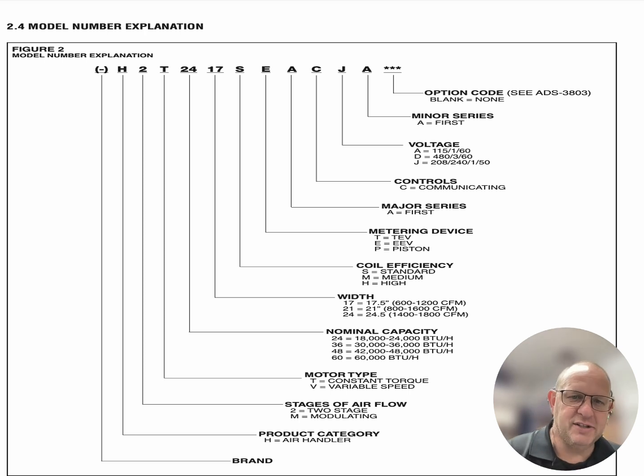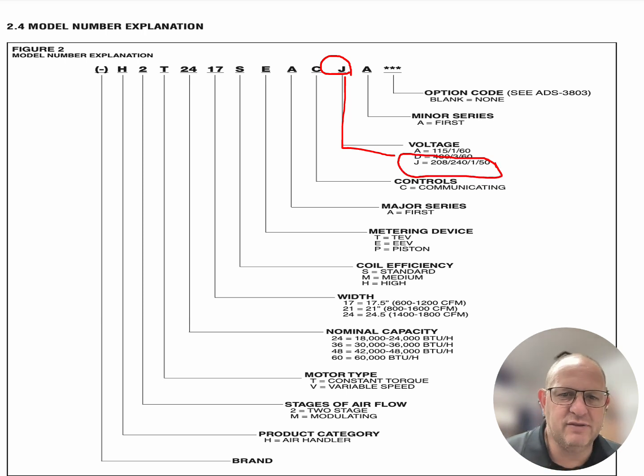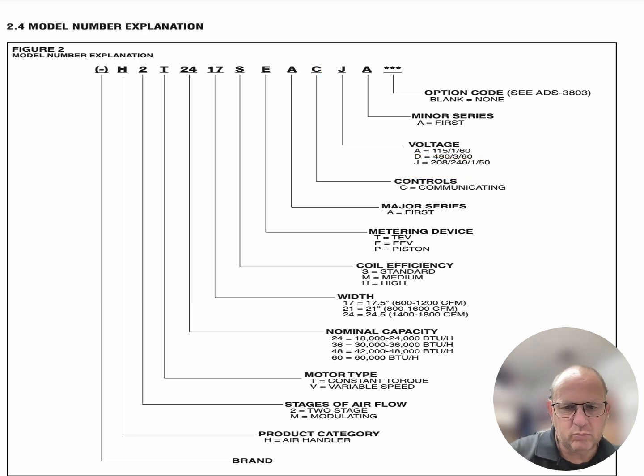Now, if I was to ask you what the voltage rating of this would be, this one in particular is a J. Come down to the J, and we can see that this actual unit must be a European unit because it's 208, 240, single phase, 50 hertz for that particular unit there. But that is how the actual model number will break down on the system itself.